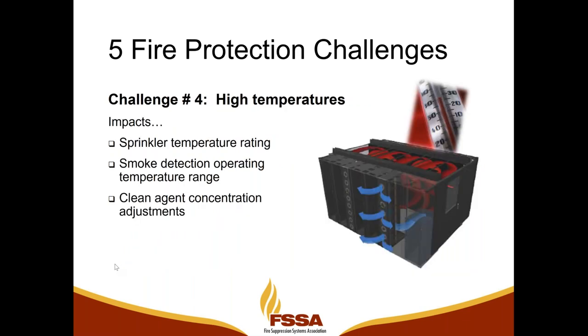Another challenge that aisle containment creates is that as we separate the cold air from the hot air, and now there's no mixing, we can exceed temperatures that fire protection equipment is rated for. In the hot aisles, high temperatures can impact the sprinkler temperature rating, the smoke detector temperature rating, and may even require some clean agent concentration adjustments.